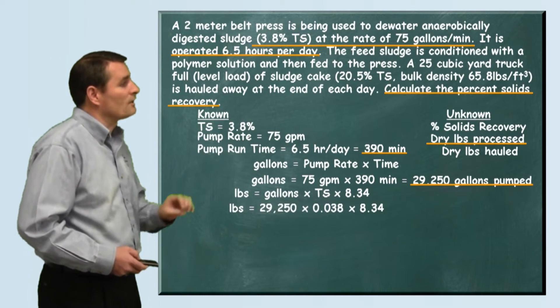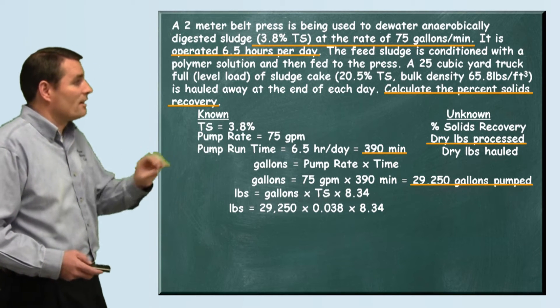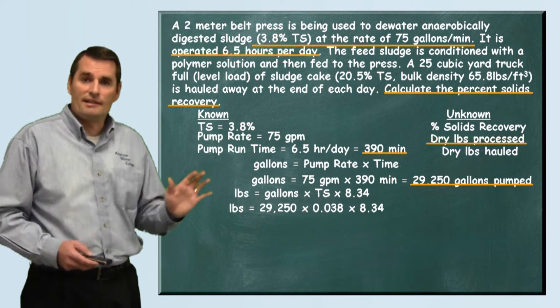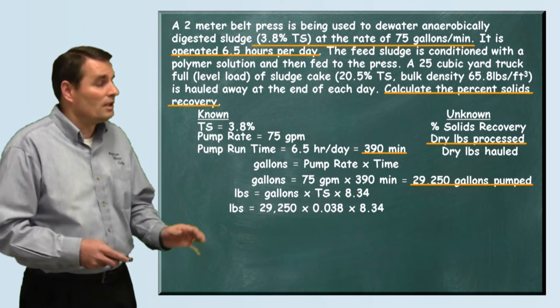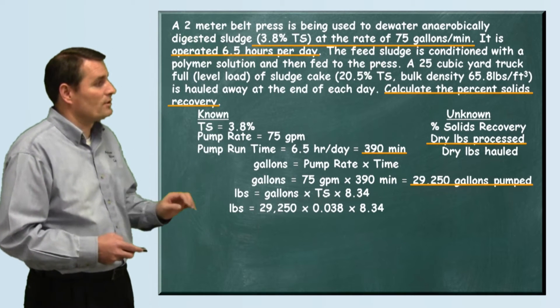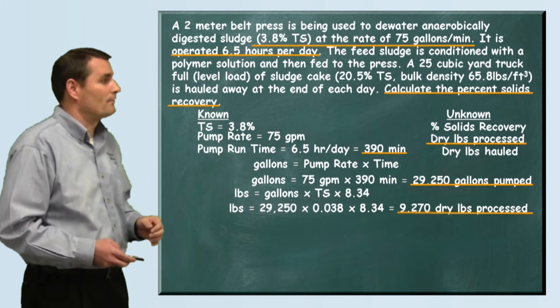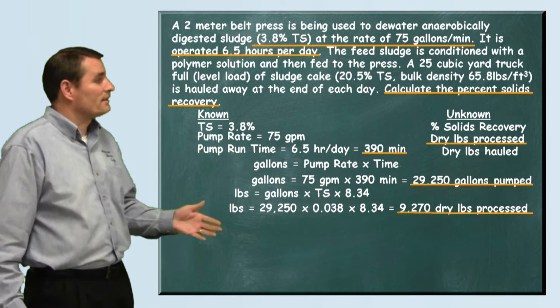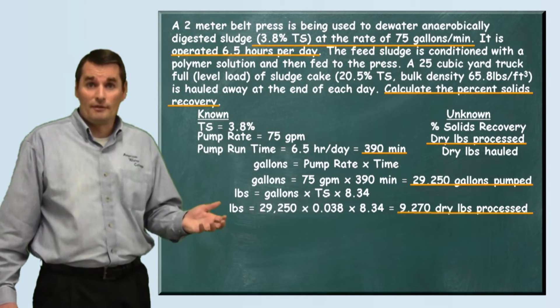When we plug in our 29,250 gallons and our percent total solids 0.038 - remember when you use percents we want to use them in their decimal form, so 3.8 percent is 0.038 - and then we multiply by 8.34. When we do that we see that we processed 9,270 dry pounds of sludge.